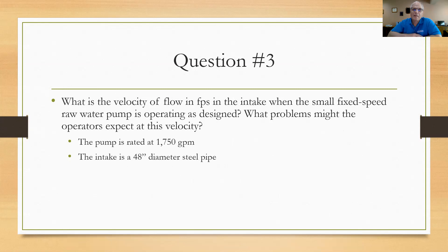We see that the intake in the table is listed as a 48-inch diameter or four-foot diameter steel pipe. So we know that the velocity always equals the flow rate divided by the square foot area or the square area. What I'm going to do is put V equal to the flow rate converted to cubic feet, which is 1,750 gallons per minute divided by 7.48 will give me cubic feet per minute divided by the square foot area, which will be 0.785 times 4 times 4. I come up with 18.63 feet per minute or about 0.31 feet per second. Now that's pretty slow.